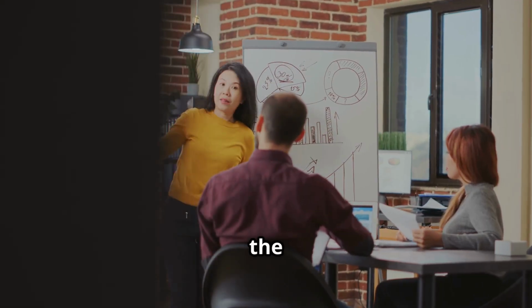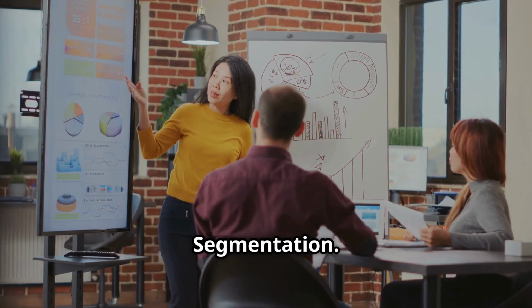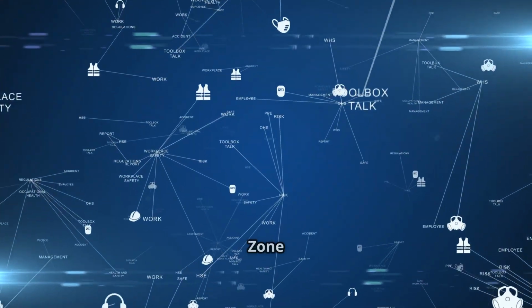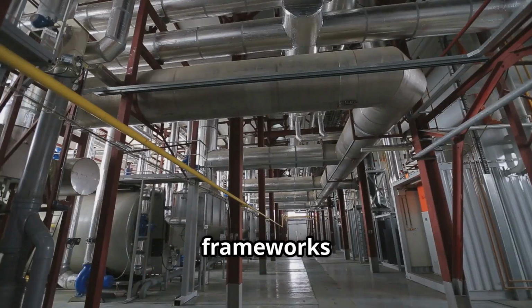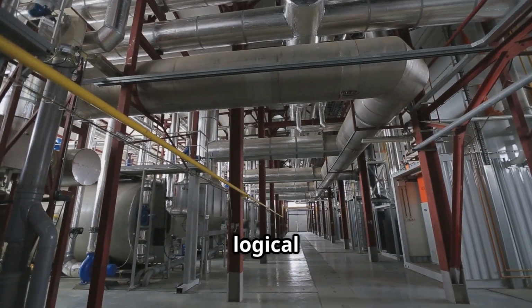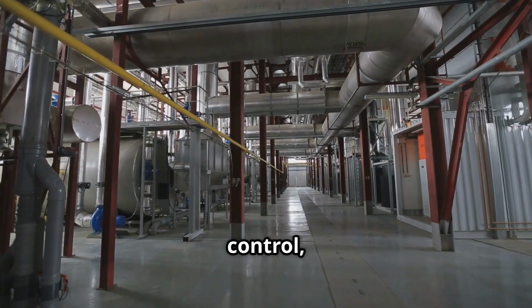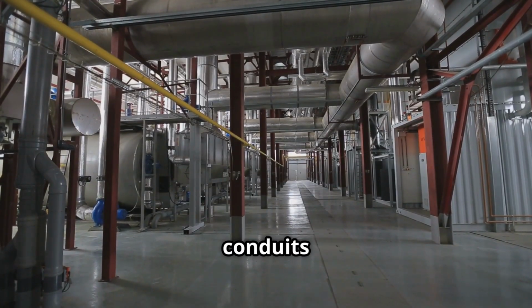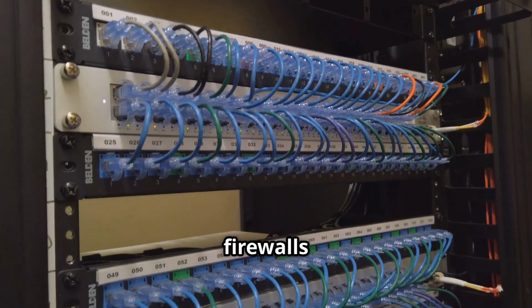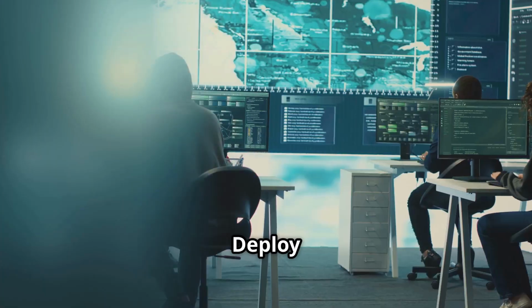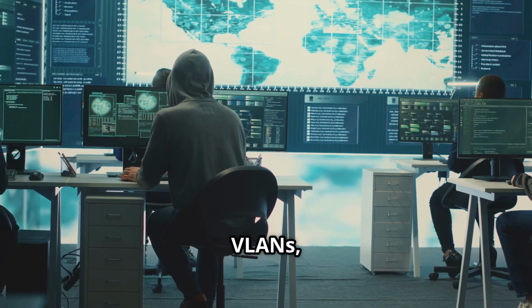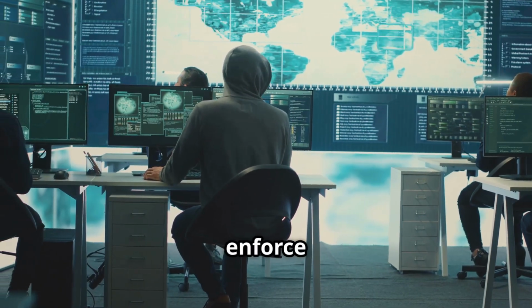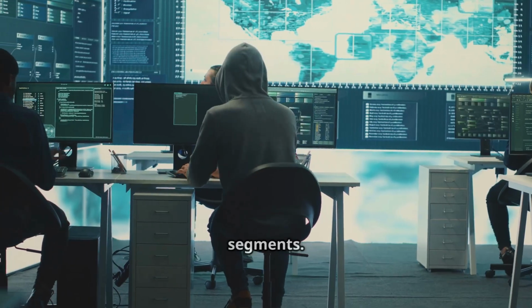Now, let's talk about the key elements of OT network segmentation. First, there's the zone and conduit model. Use frameworks like the Purdue model to create logical zones, such as safety, control, and enterprise, and secure conduits between them. Next, firewalls and access controls. Deploy industrial firewalls, VLANs, and access control lists to enforce boundaries and monitor traffic between segments.